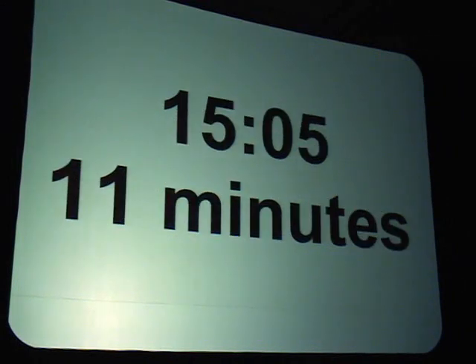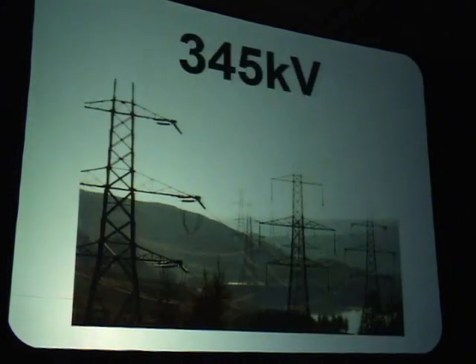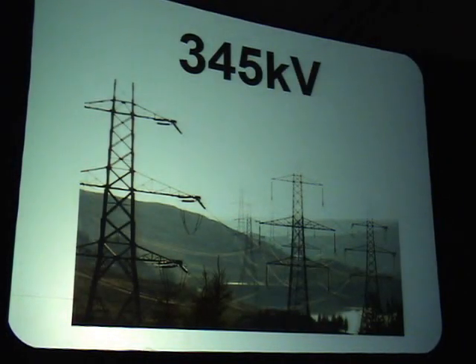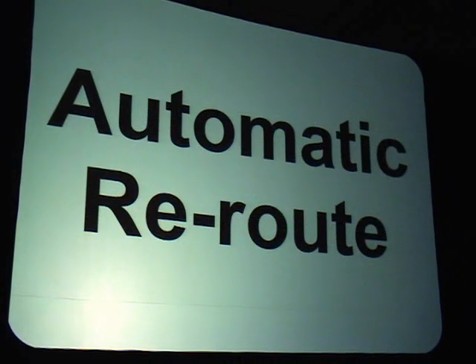11 minutes after that, with the monitoring system not looking at what's going on, one of the very, very large 345 kilovolt lines sags into a tree, the circuit breakers trip, and it goes down. Now, nobody notices this. The reason for that, first of all, is because the alarm system is down, but secondly, it's because when you build yourself a big power distribution network, you have automatic rerouting of load. So when a power line does go down, it doesn't necessarily lose you power.